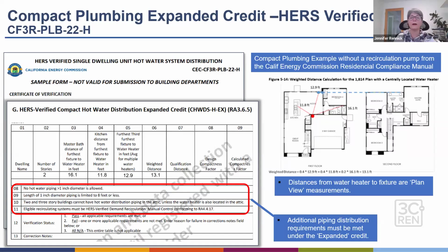Part of the reason we recommend doing compact plumbing, whether you take credit for it or not, is because a lot of times if you do compact plumbing—meaning the heat pump hot water heater is very close to the fixtures that require hot water—in those systems you often don't need a recirculation pump anyway.